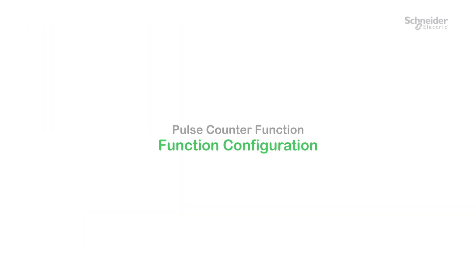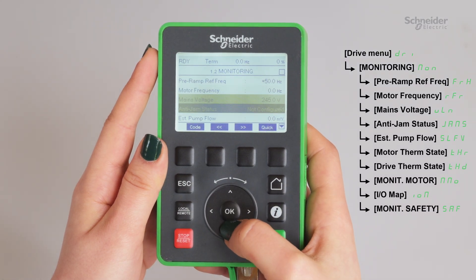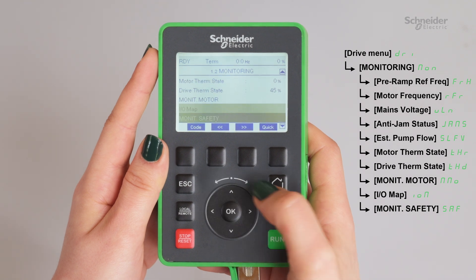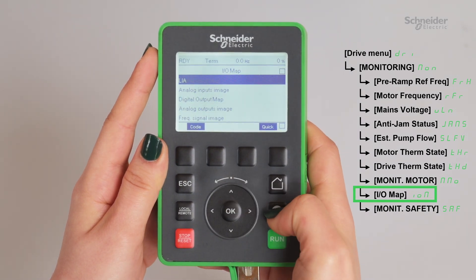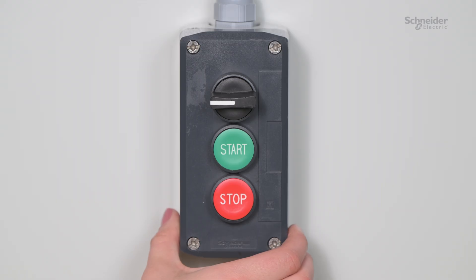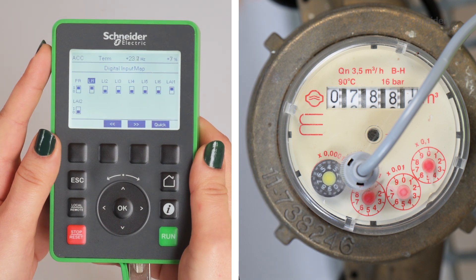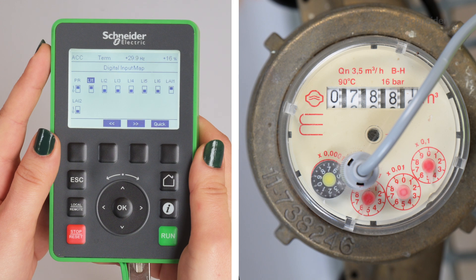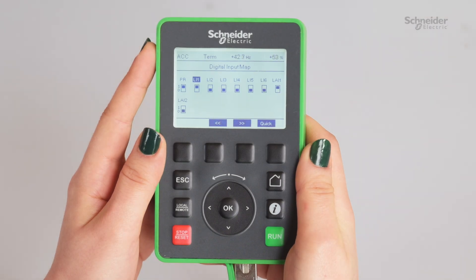Function Configuration. After wiring your installation on DI6, go to the Monitoring menu. Select Input Output Map and Digital Input Map. Start the pump and check that the pulse on the digital input is present. Stop the pump.